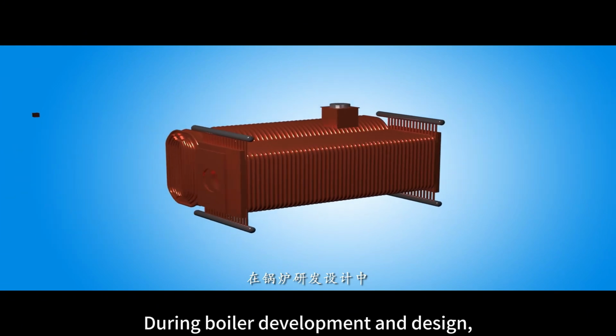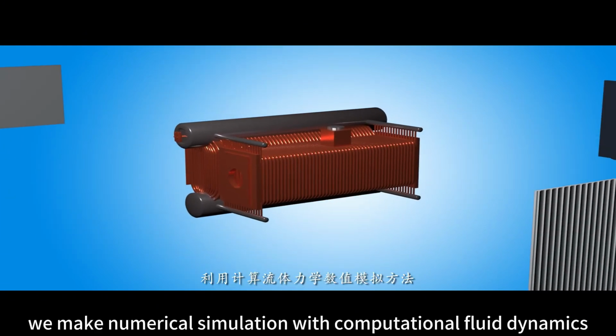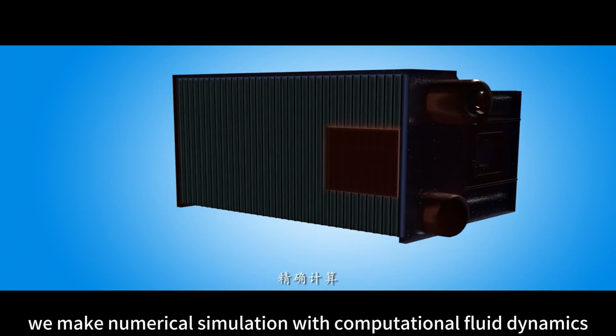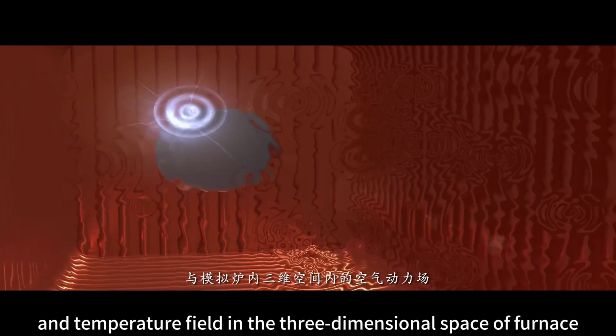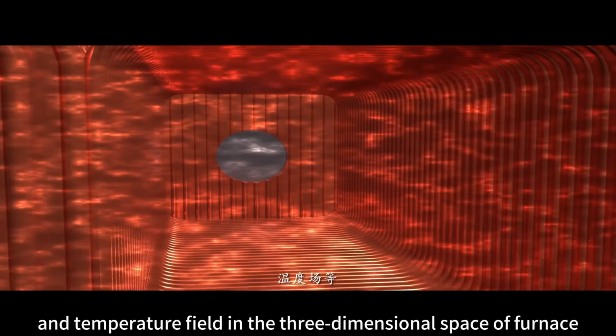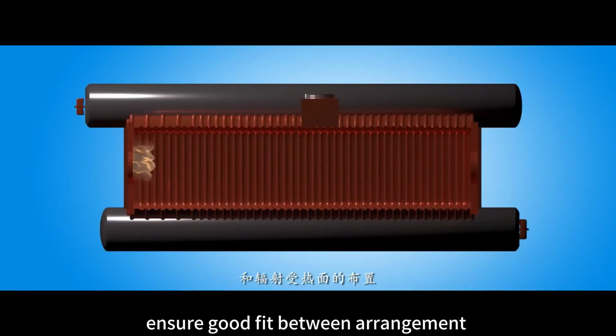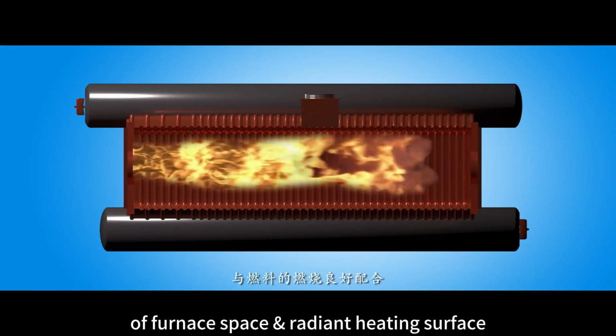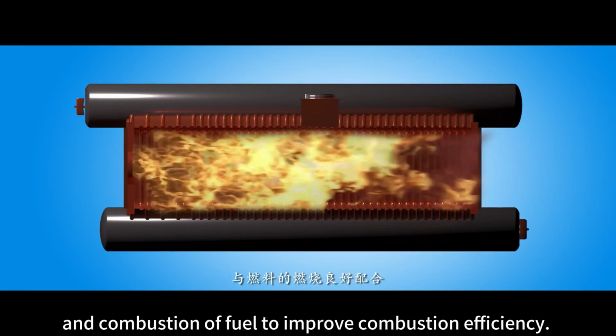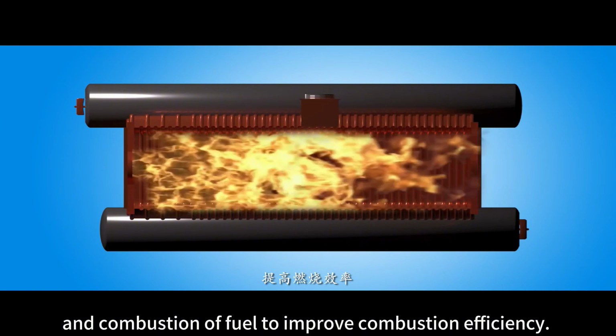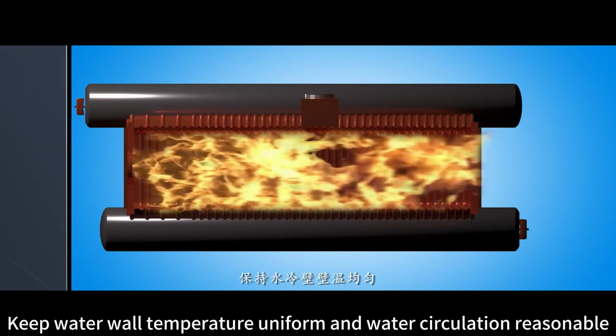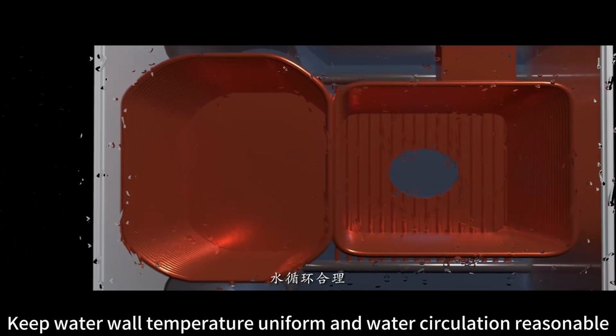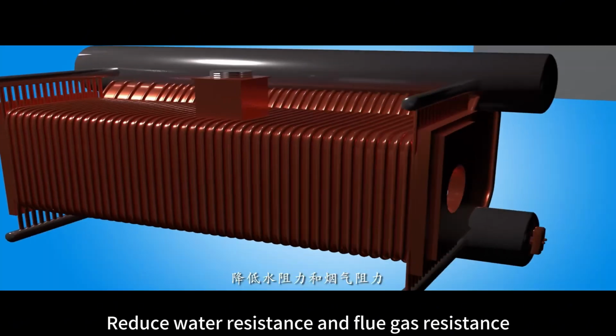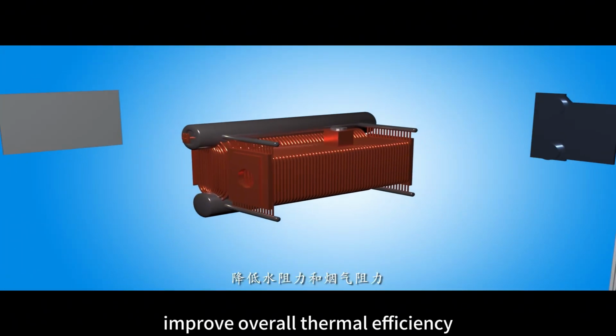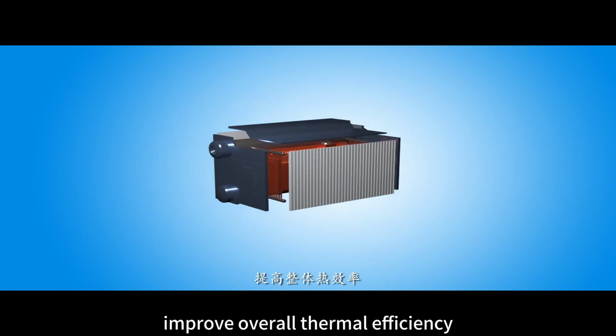During boiler development and design, we make numerical simulation with computational fluid dynamics, to accurately calculate and simulate the aerodynamic and temperature field in the three-dimensional space of the furnace, ensure good fit between arrangement of furnace space and radiant heating surface and combustion of fuel to improve combustion efficiency. Keep water wall temperature uniform and water circulation reasonable, reduce water resistance and flue gas resistance, improve overall thermal efficiency.